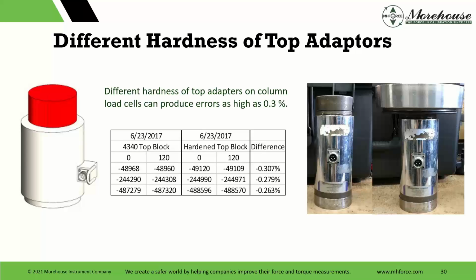When you're buying a load cell, you buy an adapter to use on top of it, and you marry that to the load cell, and therefore, whatever happens as you work harden it, as you go through 10,000 load cycles or whatever, it changes with the load cell. And it's so slow and so gradual that you keep getting it calibrated, and over time, it becomes more asymptotic, which means it just straightens out. You don't really see it anymore.